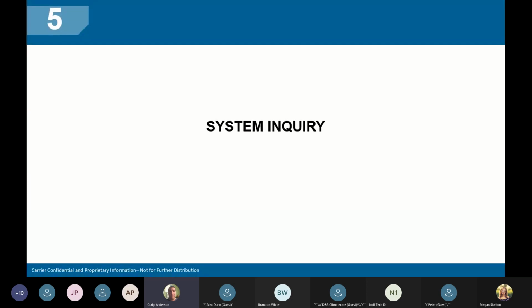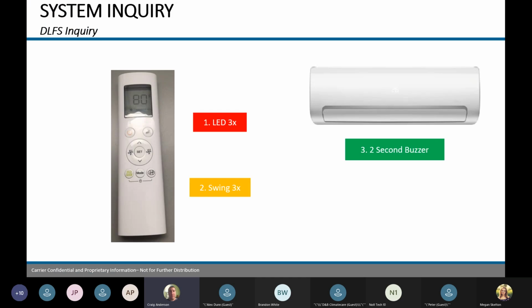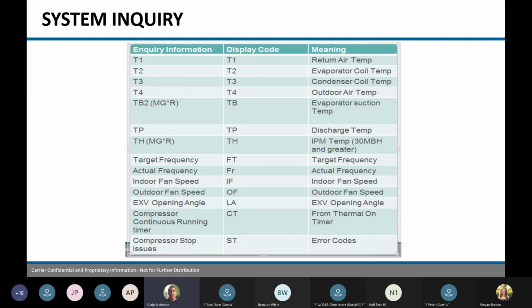System inquiry. So this is going to tell us what we can try to look at to see if we've got some nuisance stuff going on. We can get into the background of the unit to test some things. So on your main control, we're going to press the LED 3 times. We're going to press the swing 3 times. You're going to hear the unit buzz, and it's going to get us into the remote control function to test some things and look at some things of what the unit's doing. So we can do this while the unit is running or when the unit is off.